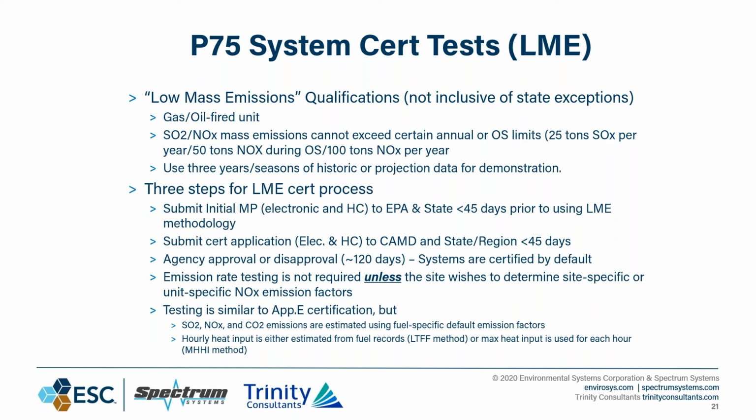I've seen it go both ways on this, and you get a lot closer to accuracy using a longer term fuel flow method than you do with maximum heat input. When they say max heat input, that means every hour is the maximum heat that you can output from the unit. Long-term fuel flow, you wind up having to go back and apportion fuel use for each hour. Anything on that, Adam?